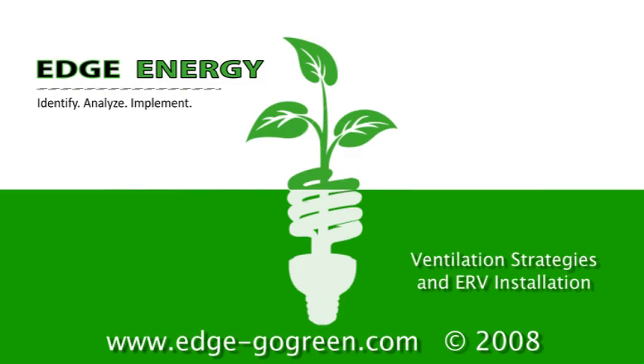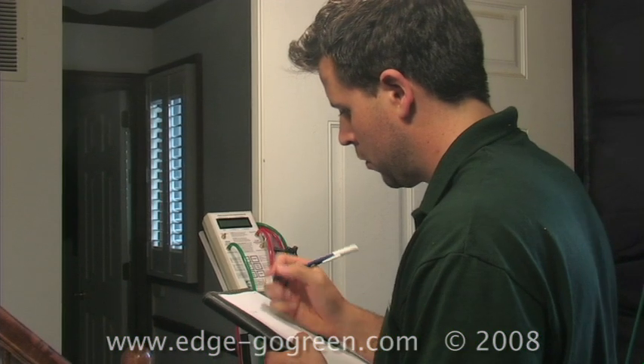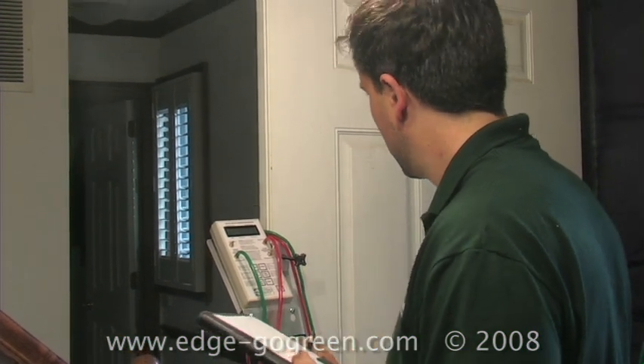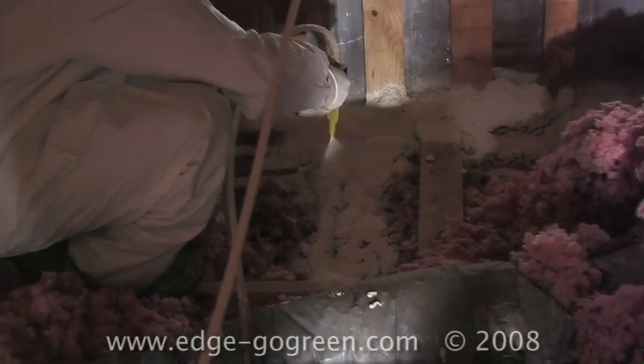Based off of the blower door test from your energy audit, we're going to come up with a threshold number. Your house has this much air leakage. For a proper amount of fresh indoor air, you need about 8 or so air changes per day. That's the entire volume of the inside of your house exchanging with the outside each and every day. If your house is over that amount, your house is too leaky.